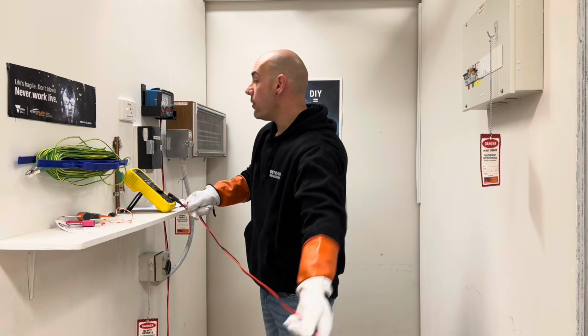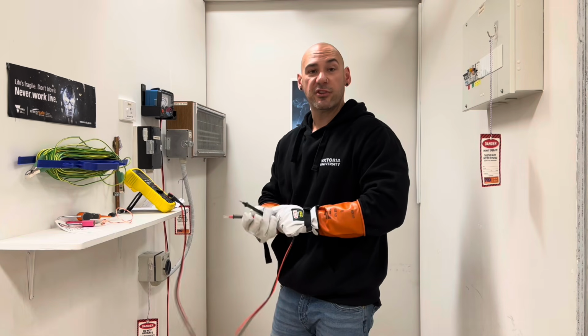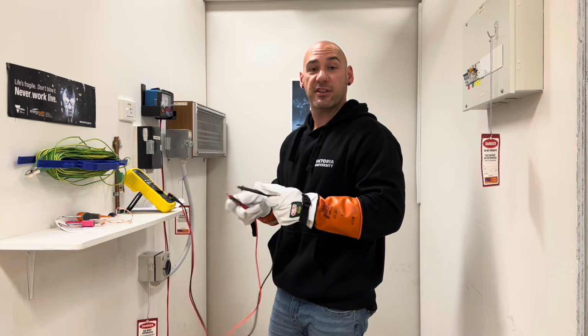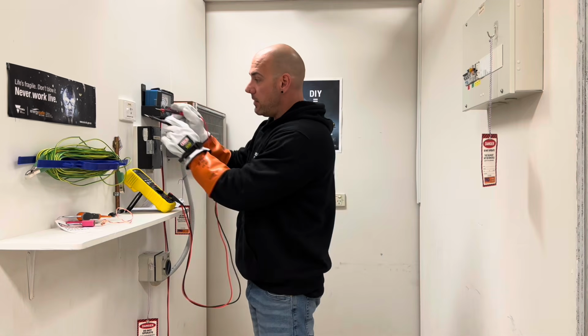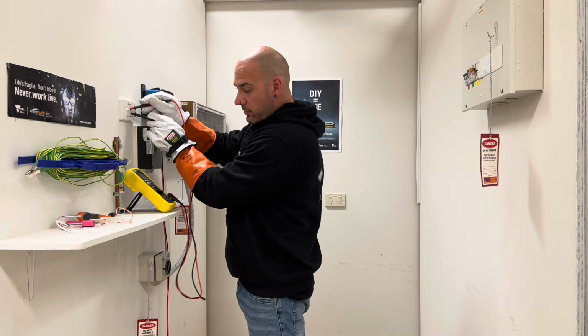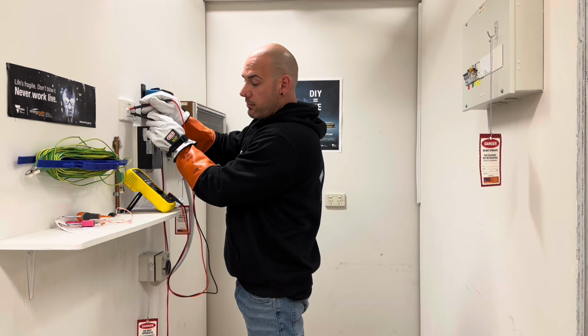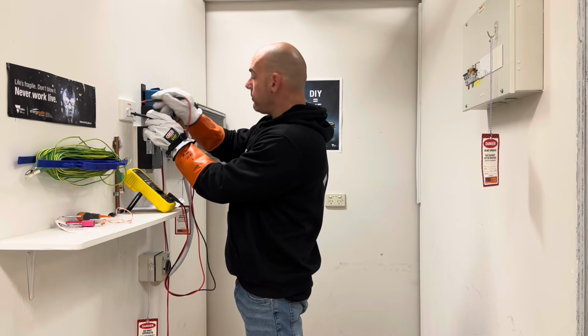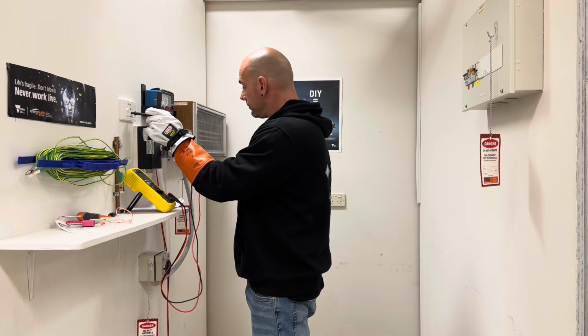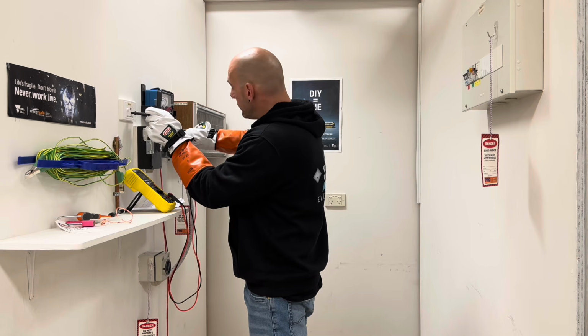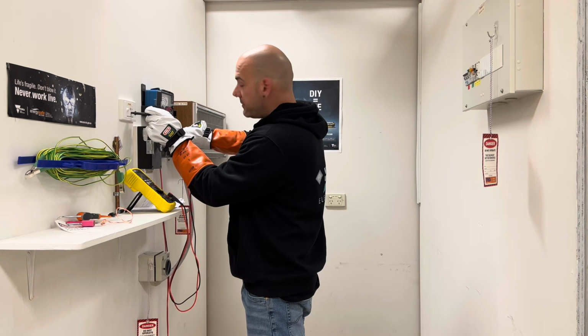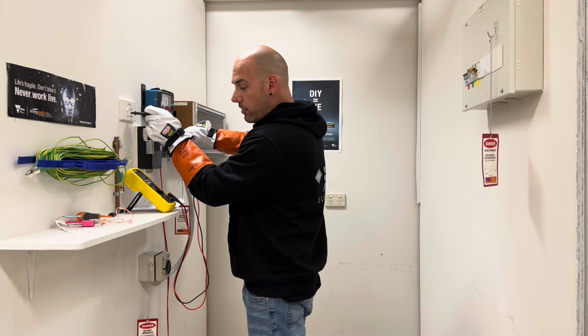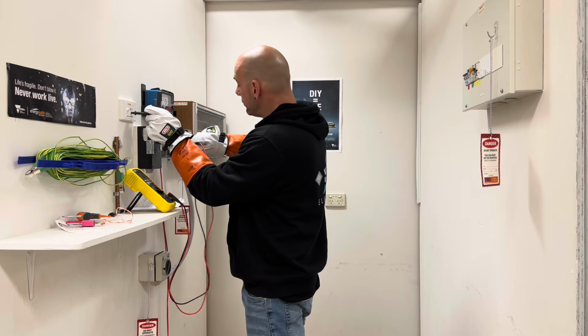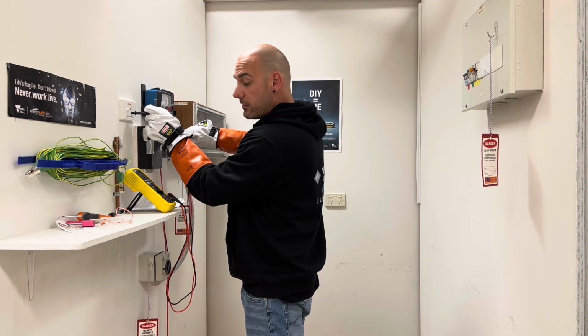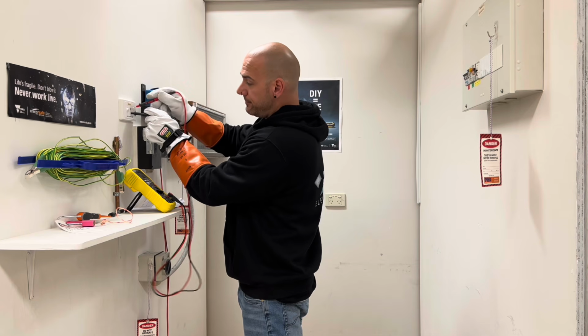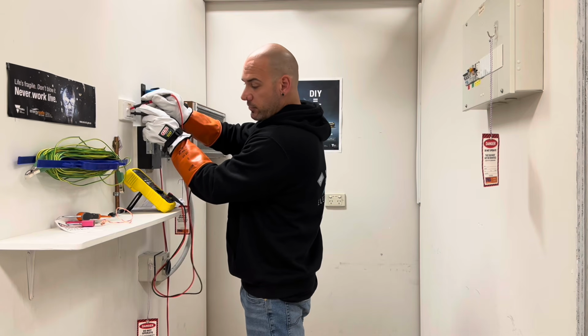We return to the appliance and we need to do a final voltage test to make sure that voltage is back at the appliance. Test on our reference voltage, and we've got 240 volts there. We test from earth to earth and we have 0 volts. Earth to neutral, 0 volts. Earth to active, which is 240 volts, which is good. Test our tester, we've got 240 volts.